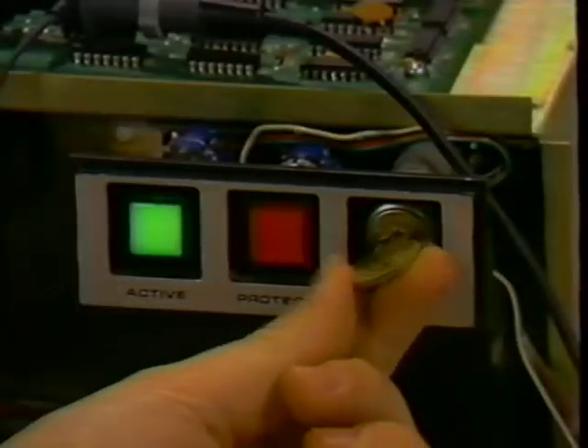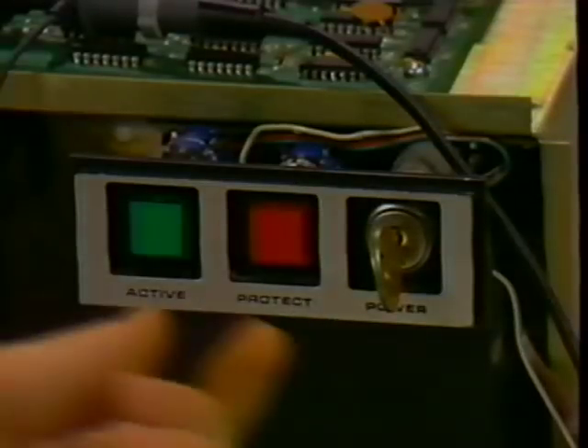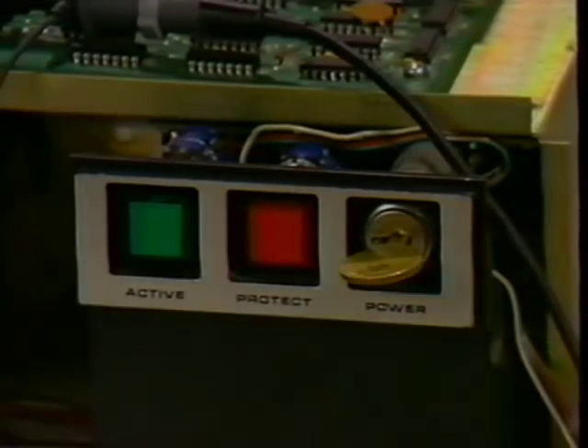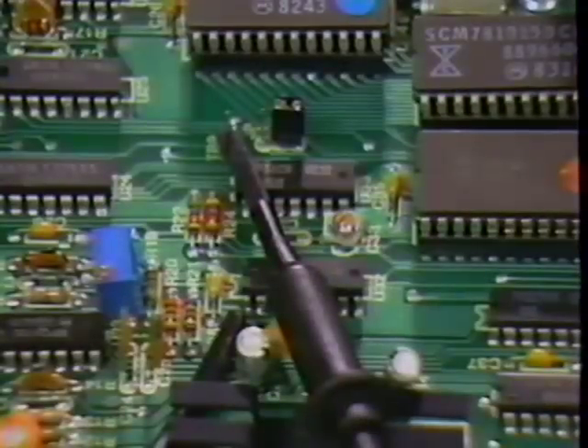The next alignment to make is input bias and the output frequency of the read VCO when no data is being read. The purpose of this adjustment is to make the VCO output frequency as close as possible to the nominal read data rate. Remember to turn the drive off for 30 seconds and then back on to verify that the VCO locks on to the correct frequency. Otherwise, it may operate at an incorrect rate, which will make it impossible to decode incoming data. If the frequency is not correct, readjust the VCO.